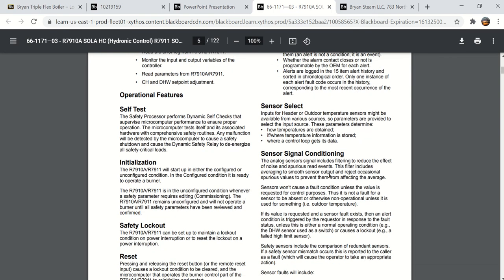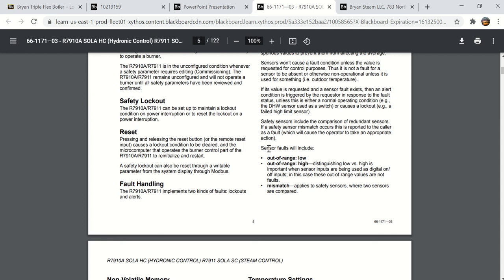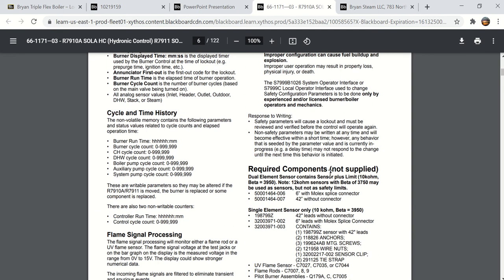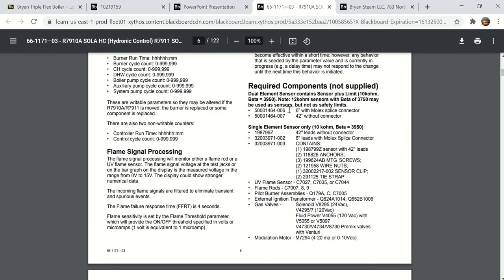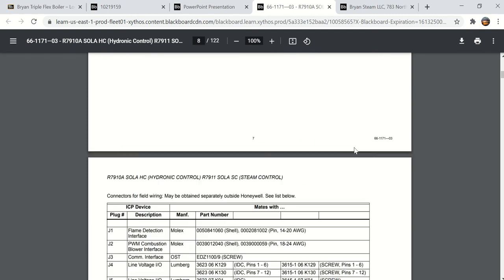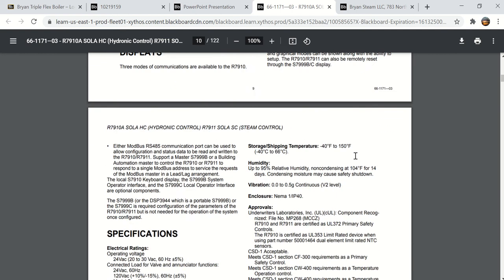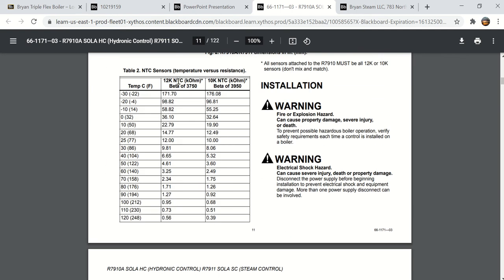Some other things about the controller: if you had a sensor fault, maybe you wanted to test and see if a sensor was good, you would need to unplug it and then go to the chart that we looked at earlier and measure the resistance of that sensor. If you left the boiler turned on when you unhook that sensor, it's okay, you can do that, but you would get a fault. It would say the sensor is out of range, either low or high, depending on whether it's a negative or positive temperature coefficient. I probably should explain that. On the sensors here, they were a negative temperature coefficient sensor. NTC. If it says PTC, that's positive temperature coefficient.